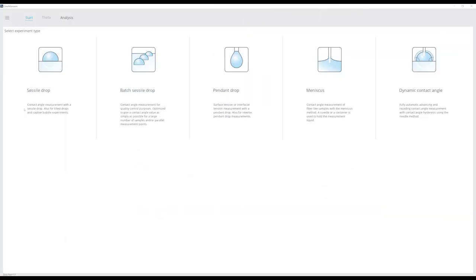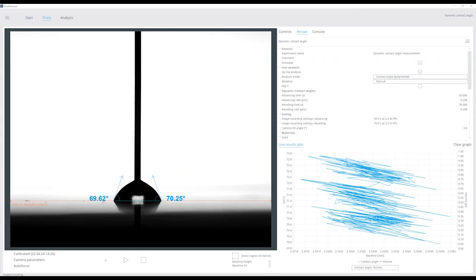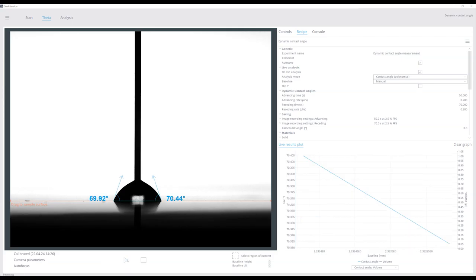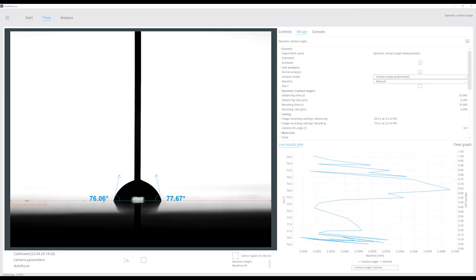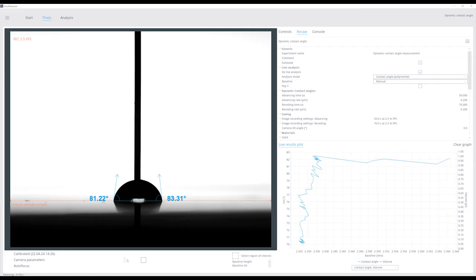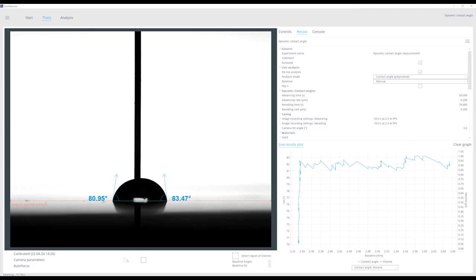Advancing and receding contact angles can be easily measured with the automated dynamic contact angle method. An initial drop can be created and placed on the surface. The needle is then brought very close to the surface and in the middle of the drop. The measurement is fully automated as advancing and receding times, as well as dispense and liquid withdrawal rates can be separately set in the recipe.